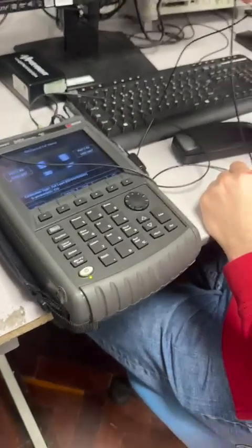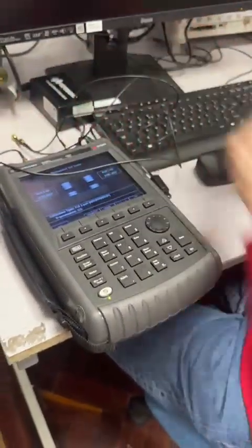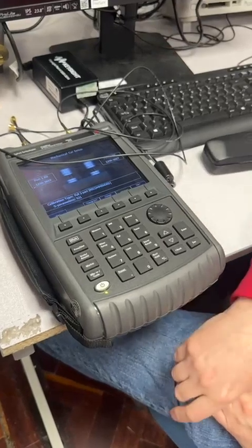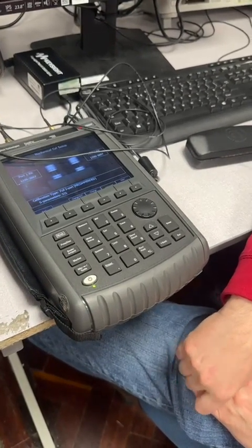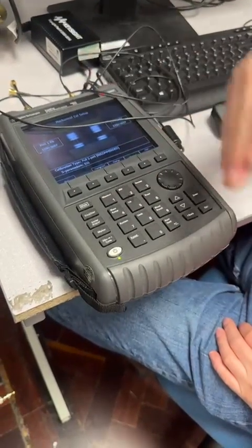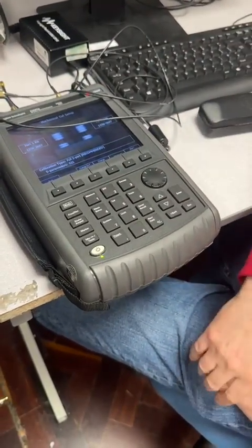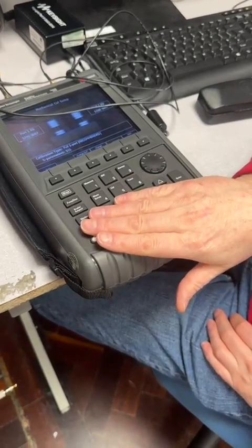Okay? But very difficult to get a true absolute accuracy because you're using those standards. So you can imagine now how tight the tolerances need to be on the actual perfect standards, and that's why they're expensive. That's why you're talking thousands of pounds for those cal standards, because they have to be repeatable across the globe. All right?